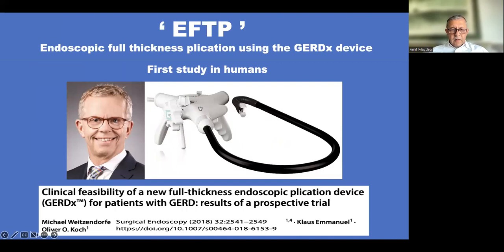You see here, this device has got a handle. It's very big, thick. It's bigger than the shaft of an endoscope. And at the tip of this device, there are two arms. At both the arms, we can attach staples. One side is the staple, second side is the receiving end of the staple. And this is a pledget on the other side. So this device is passed inside the stomach over a guide wire. So you have to first pass an endoscope into the stomach, leave a stiff guide wire, and over this device is railroaded. After railroading, through the device, we pass inside an ultra-thin endoscope. So you take out the guide wire and you pass an ultra-thin endoscope, because this device doesn't have any optics. So the endoscope comes out through the device over here.